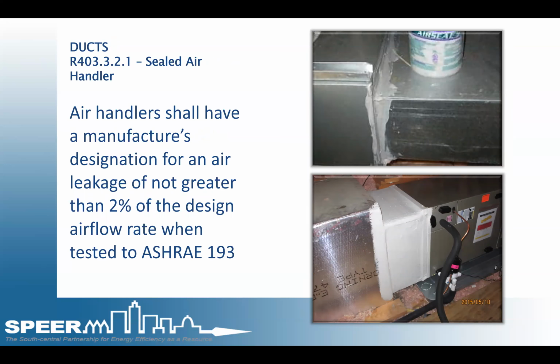403.3.2.1, sealing of the air handlers. All seams between furnace and air handler, plenums, filter boxes and coils must be sealed, and furnaces and air handlers must be tested to show that the cabinet leaks no more than 2% of the designed airflow. So for example, if a furnace or an air handler is a 3-ton, it gives us an airflow of 1200 CFM, which is 400 CFM per ton times 3. So the allowable leakage just by the cabinet, by the manufacturer, is 24 CFM.